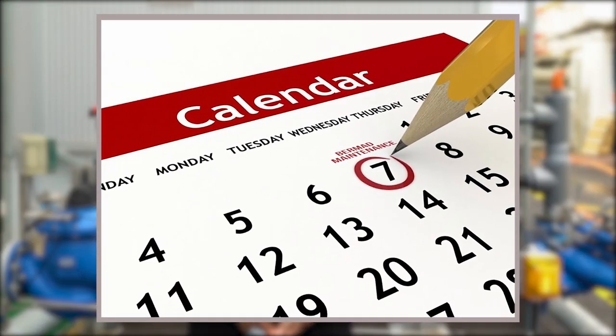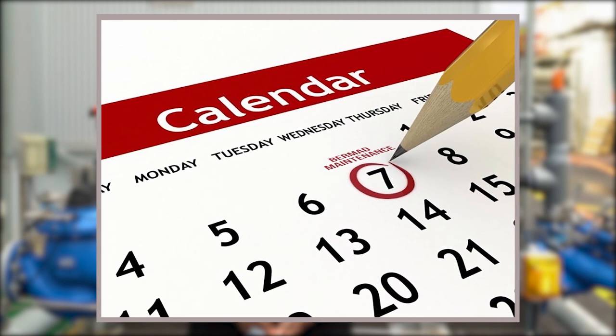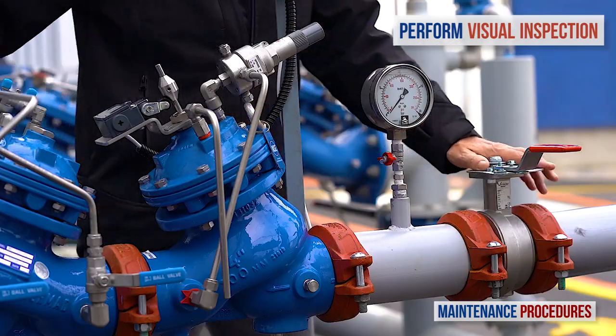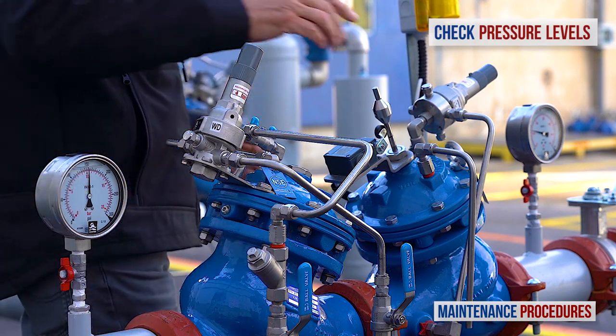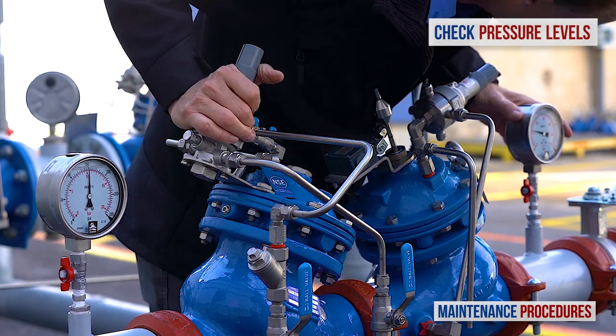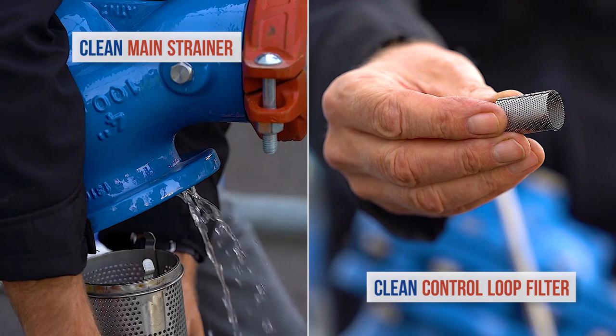Now let's discuss maintenance procedures for the Bermad pressure reducing station with shut-off valve. Note that your schedule for preventative maintenance depends on actual conditions of use and the station's environment. Here we discuss the schedule suited to a valve operating under average conditions. On a weekly basis, perform a visual inspection of the station and check for leaks and external damage. In addition, observe the unit's pressure gauges to make sure that the pressures upstream and downstream are as they should be. Once a year, close both isolation valves and clean the main strainer and the valve control loop filter. Every three to five years, inspect the internal condition of the pressure reducing valve.